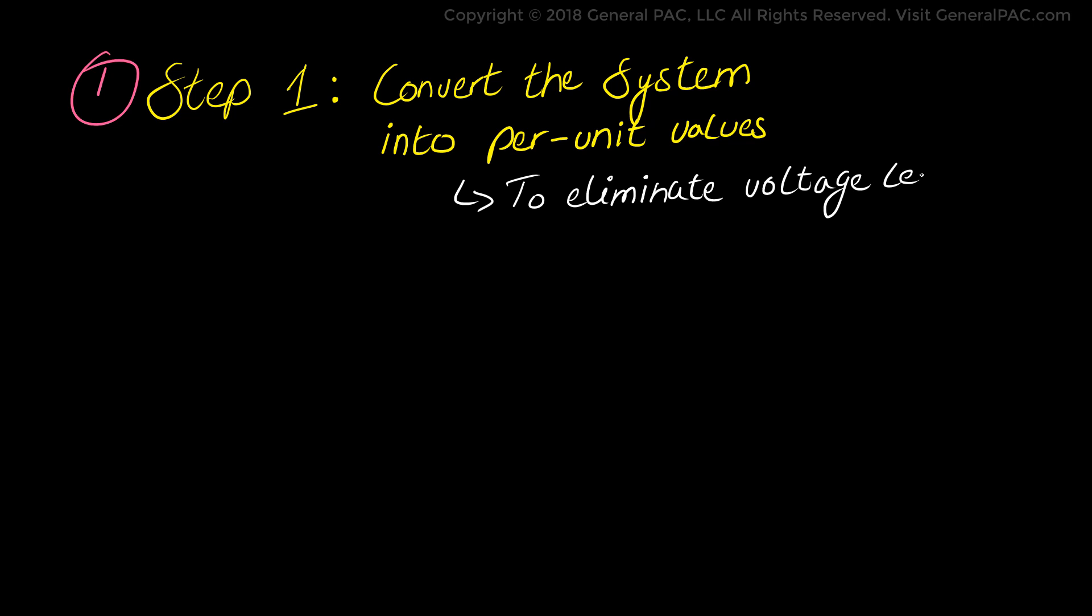So in step 1, the first step is to actually convert the system into per unit values. Now the reason why we convert it into per unit values is because we want to eliminate the voltage levels that occur in power systems due to voltage transformation. So if you have a low voltage to a high voltage power transformer or a high voltage to a low voltage power transformer, it adds an incredible amount of complexity when calculating fault currents.